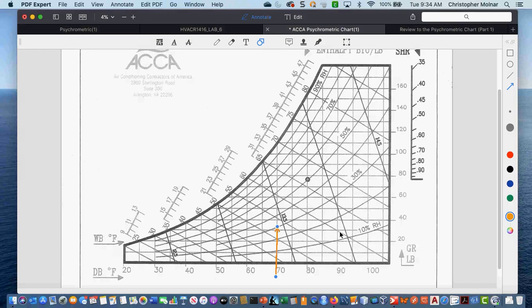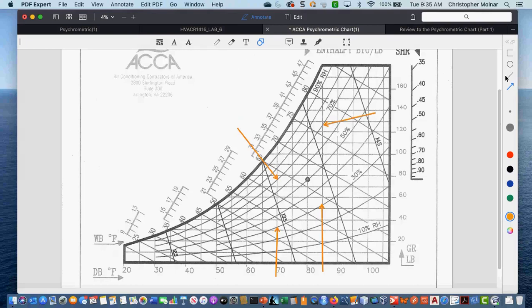The comfort zone dry bulb temperature goes up to 80 degrees at 30% humidity. At the top level, with 85 degrees, we don't want to go above 70% humidity. At the lower end, 70% humidity at 70 degrees. Those are the four corners of what is considered comfortable for humans.